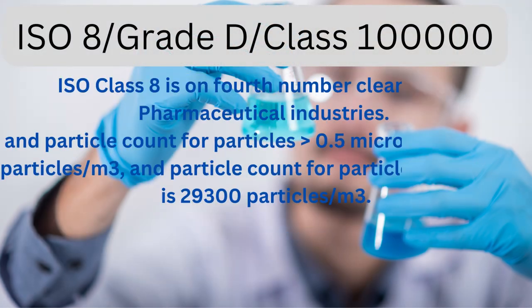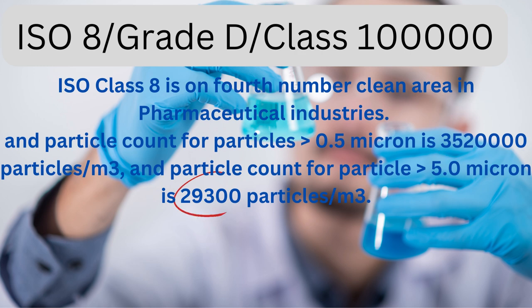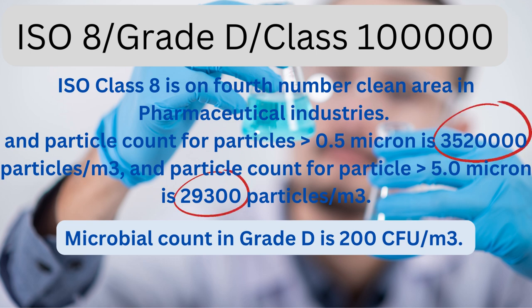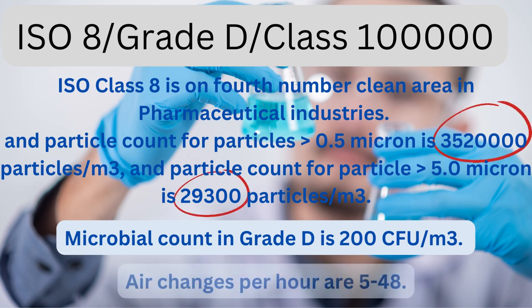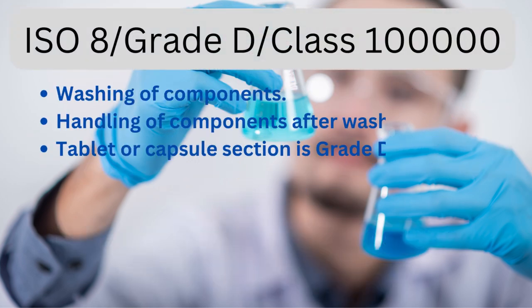Fourth is Grade D, corresponding to ISO 8 or Class 100,000. ISO class 8 is the fourth clean area in pharmaceutical industries. Particle count for particles greater than 0.5 micron is 3,520,000 particles per cubic meter, and particle count for particles greater than 5.0 micron is 29,300 particles per cubic meter. Microbial count in Grade D is 200 CFU per cubic meter. Air changes per hour are 5 to 48. Grade D is used for: washing of components, handling of components after washing, and tablet or capsule section is Grade D at rest.